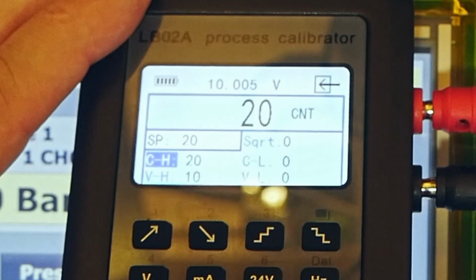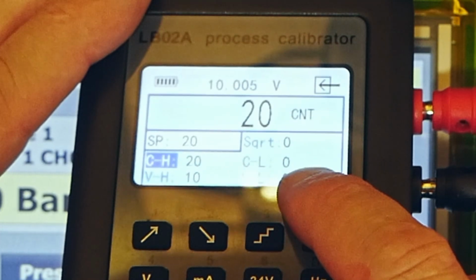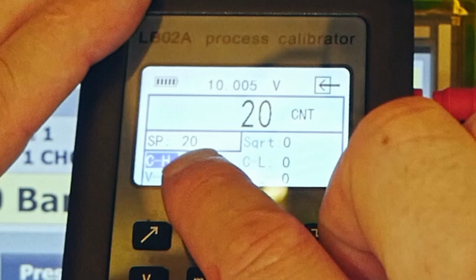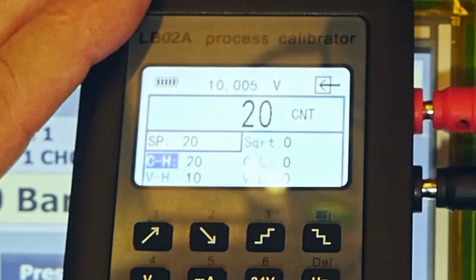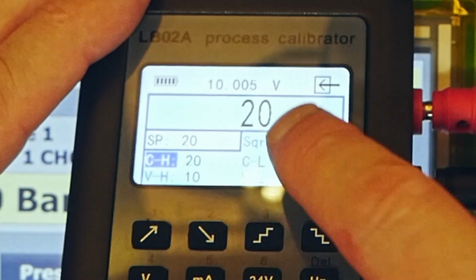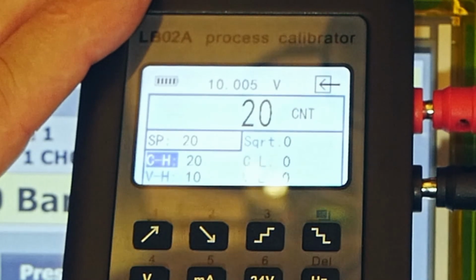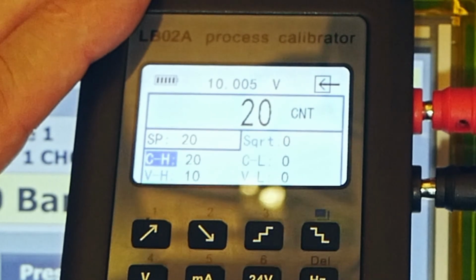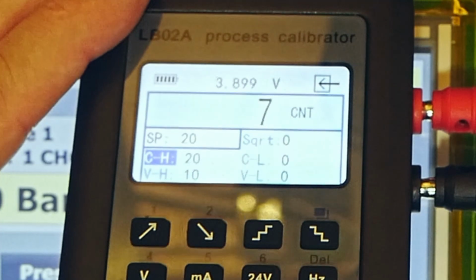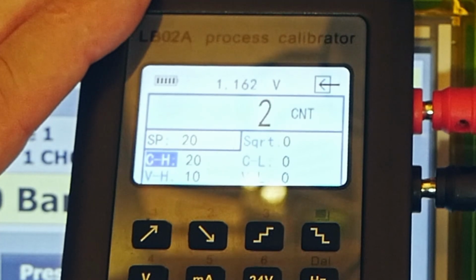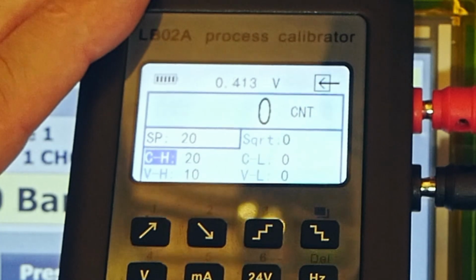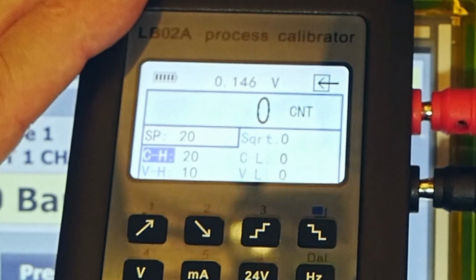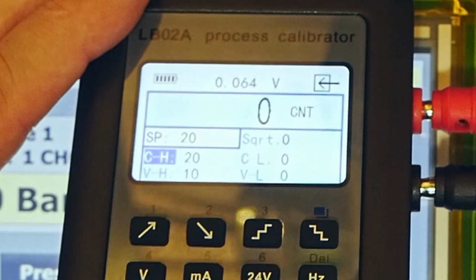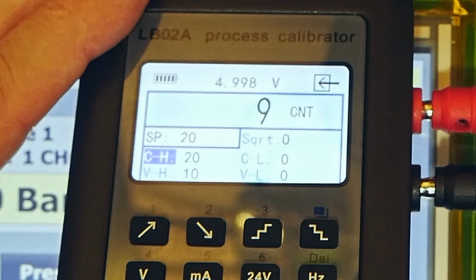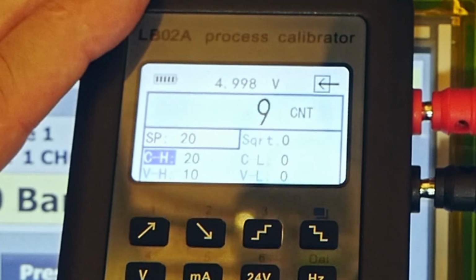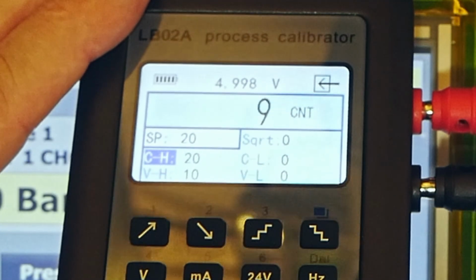So okay, my scaling here is low level 0 bars, high level 20 bars. And right now I am providing 10 volts, so as you can see, it counts 20. If I go with my bench power supply to 0, okay, it counts 0, so that is correct. Right now I will go with my bench power supply to the middle of the range, 5. It should show 10.